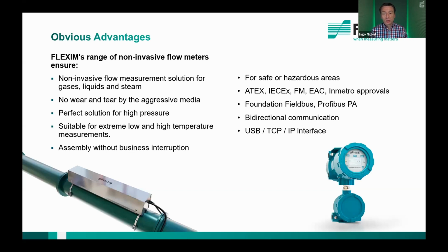Measuring at very low but also very high pressures, thick pipe walls and exotic materials, as well as badly manufactured pipes, is not a challenge for a clamp-on flow meter from Flexim. We also support a lot of process interfaces like Profibus, Foundation Fieldbus, HART, and we are covering all explosion-proof environments: ATEX Zone 1, Zone 2, FM Class 1 Div 1, Div 2. So we have a complete package for flow measurement equipment within chemical plants.